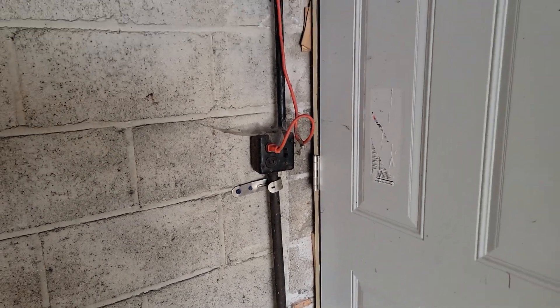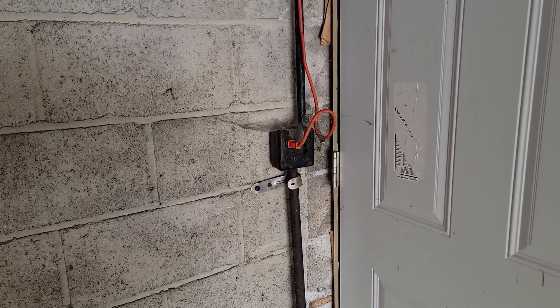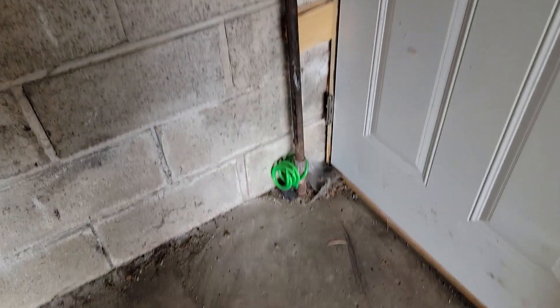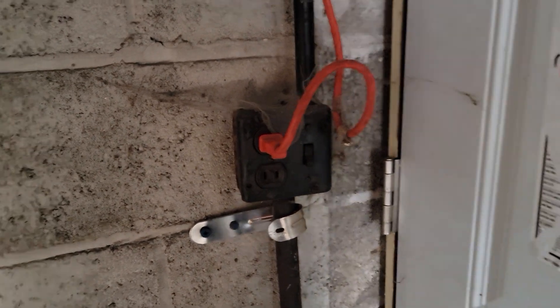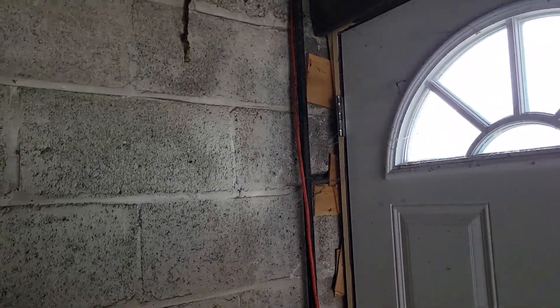I start my day in Chicago doing a single-family home inspection. While looking at the panel, I noticed cloth wire and I believe it was feeding the garage. When you come into the garage, you've got to have a GFCI at that receptacle. You can see the steel pipe — conduit — in here.